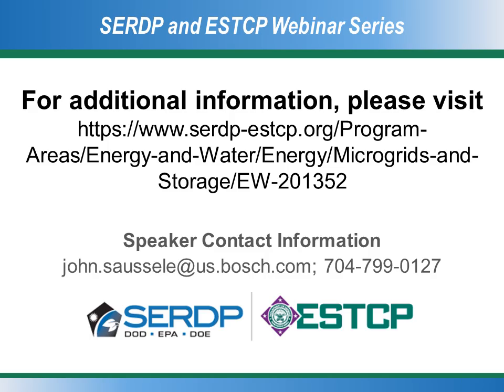Yeah, so I mentioned that we reduce the electronics, but more specifically, we reduce the conversions AC to DC, which require electrical components called electrolytic capacitors. And electrolytic capacitors have a wear mechanism. So after a period of time, and it can be calculated, they will eventually lose capacitance and fail. In lighting, for example, many facilities are used to changing out fluorescent light bulbs. If the electronics in a fluorescent light, called the ballast, fails once in a while, it wasn't a big deal. You have crews up in the ceiling changing these fluorescent tubes anyway.